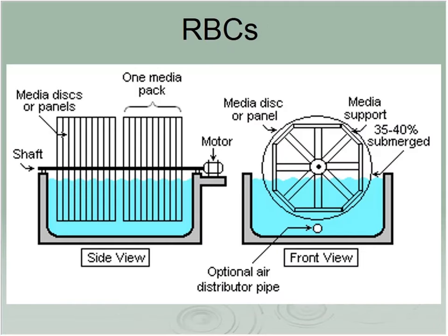And these discs slowly rotate through that vat of wastewater. About 35% of those discs are immersed in the wastewater. They turn very slowly, a couple RPM. So the bugs go down, they get their food, they come up, they get their air, they get down, they get their food, they come up, they get their air, they're happy.